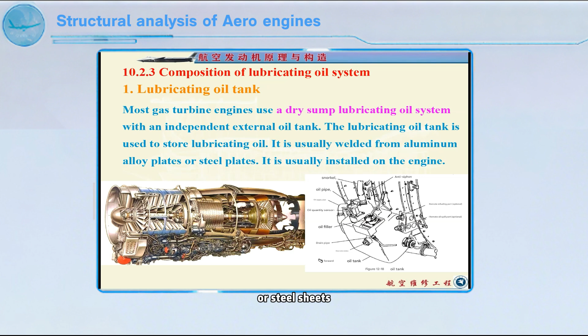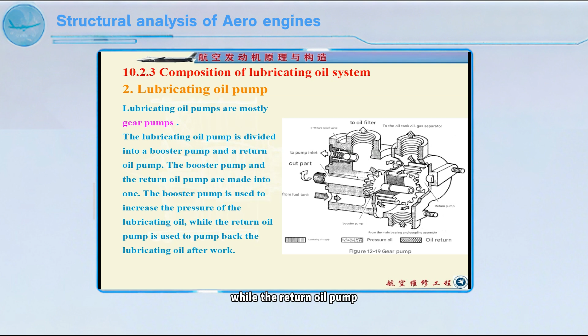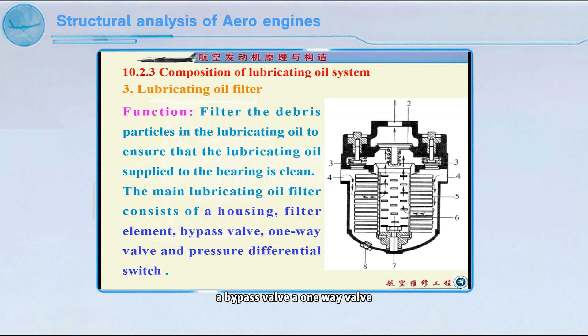Most lubricating oil pumps are gear pumps, as shown in the figure. Lubricating oil pumps are divided into booster pumps and return oil pumps. The booster pump and return oil pump are integrated, and their function is to increase the pressure of lubricating oil, while the return oil pump is to pump back the lubricating oil. The function of the oil filter is to filter the debris particles in the oil so that the oil supplied to the bearing is clean. The main oil filter, shown in the figure, consists of a housing, a filter element, a bypass valve, a one-way valve, and a pressure difference switch.